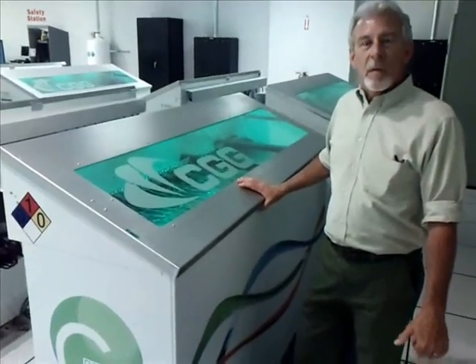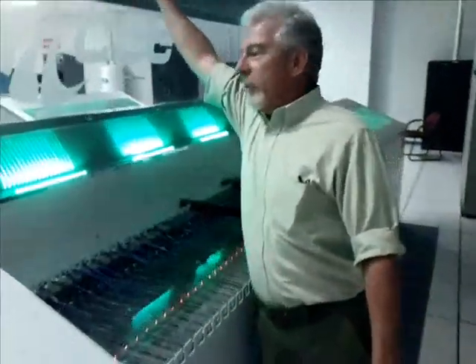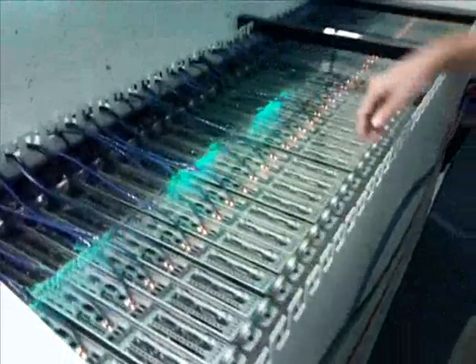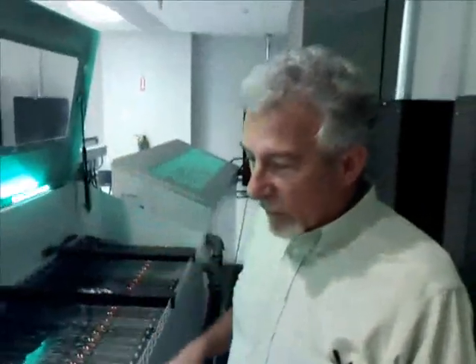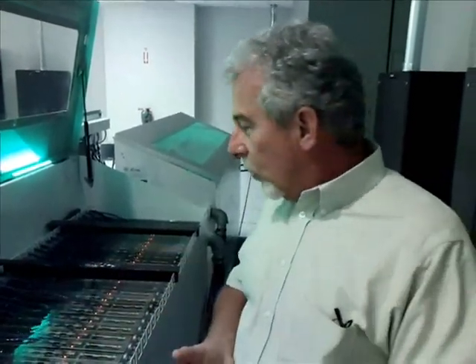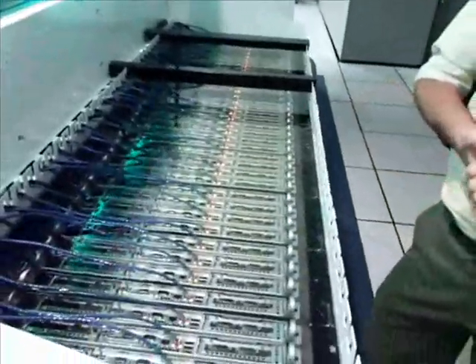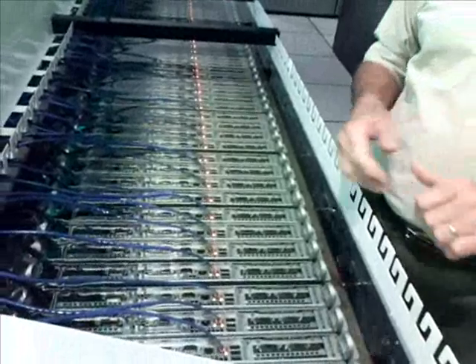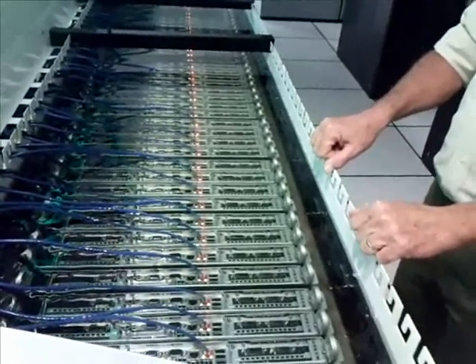This is one of the CGG liquid-cooled tanks. Inside, it's the equivalent of a 42U rack turned on its side. You can see that oil is actually flowing through — the liquid cooling is moving through here. We have a pump module in the background, basically a large heat exchanger that takes the heat from the oil to a heat exchanger and loses it into the chilled water. The oil moves at variable speed depending upon the load on the rack. We're using 1U modules, so we're actually getting 42 servers in the rack itself.